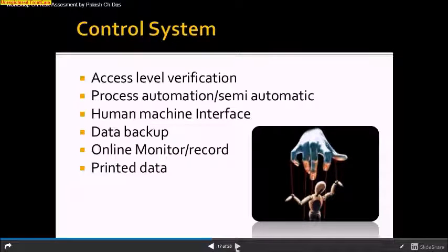Human machine interface, this is HMI. You need to look at how the HMI is working, whether the screens are okay or not, whether the language is English or your regional language. Data backup: we should check what the conditions of data backup are, whether it is electronic data backup or hard copy data backup. There is a possibility of a LAN, so we can pull the data from another system to your main server. Online monitoring and records: how you monitor the records online. And printed data: how you want the data to be printed. Sometimes in certain cases we need a checked-by sign, a done-by sign, and a company logo. That needs to be designed and proposed at the initial level. Otherwise we will struggle. Once you procure the machine and then propose the changes, it will hamper our productivity.